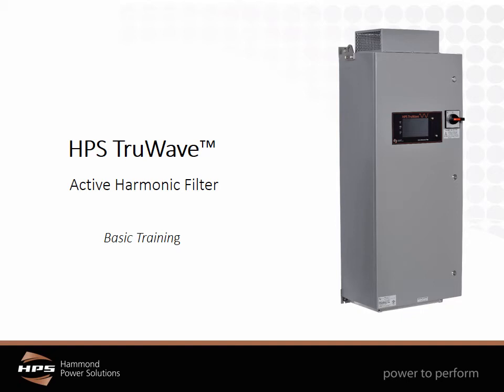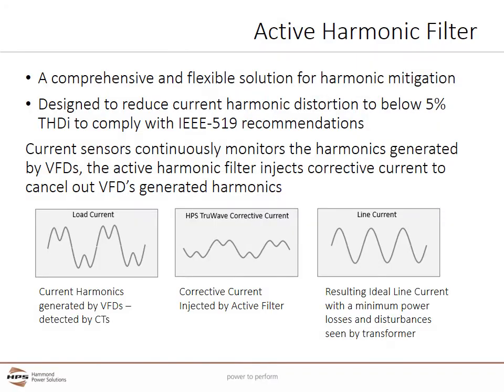Welcome to basic training on HPS's TruWave Active Harmonic Filter. An active harmonic filter provides a comprehensive and flexible solution for harmonic current mitigation. Active harmonic filters are designed to reduce current harmonic distortion to below 5% to comply with IEEE 519 recommendations.